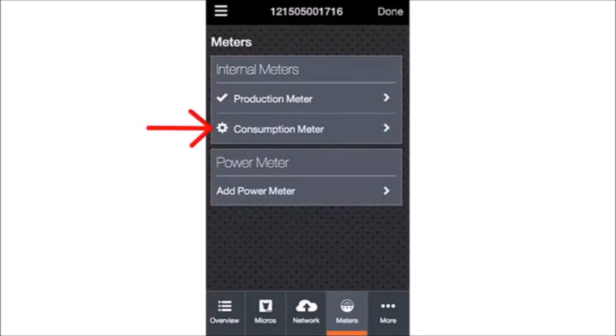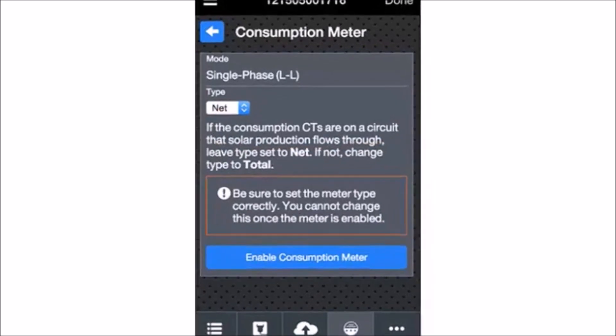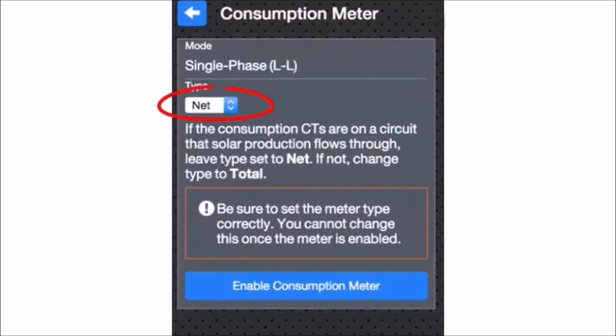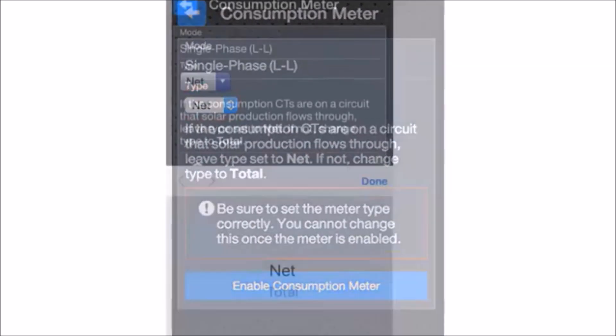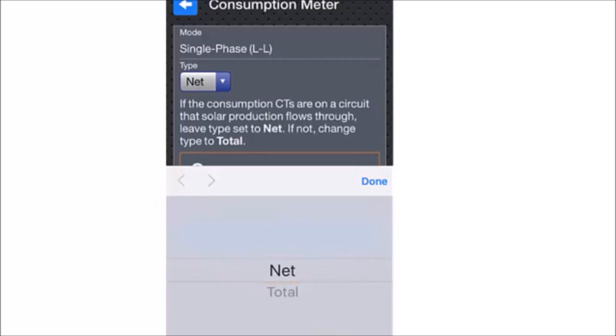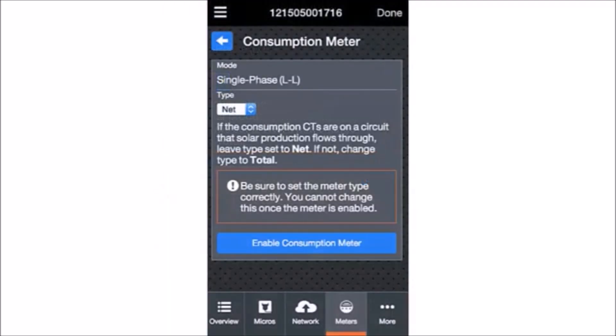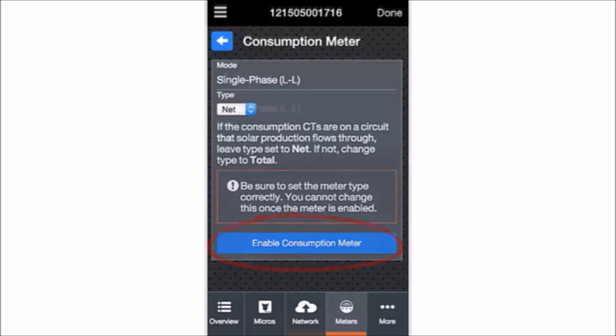Note the gear icon next to Consumption Meter. This indicates that the consumption meter needs to be configured. Now tap Consumption Meter. Select the consumption meter type based on the electrical configuration at the site. Does the circuit passing through the consumption CTs include load with solar production? If so, select Net. If it is load only, select Total. Please be sure to set the meter type correctly before tapping Enable Consumption Meter.